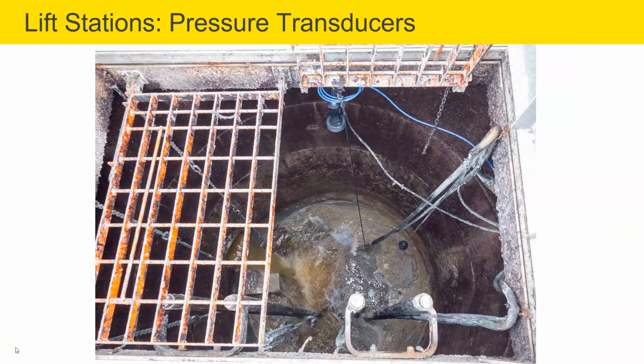Here we replaced a pressure transducer that needed to be pulled and cleaned every 3 days. The WL61 has been in there for over 3 years and has not been touched since it was installed, saving the customer thousands of dollars and making this radar unit free just from their maintenance ROI alone.